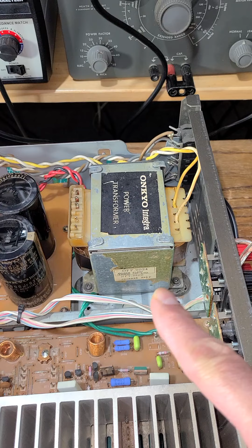I tested the first two, and it turned out the primary winding was good. The third had no continuity, and I believe that was the other end of the thermal fuse. So since I couldn't access the thermal fuse directly, I bypassed its connections. Once I did that, I tested the primary - fine - and powered up the transformer on the bench. All the primary and secondary voltages were good, no problem. The secondaries had all the required voltages needed.